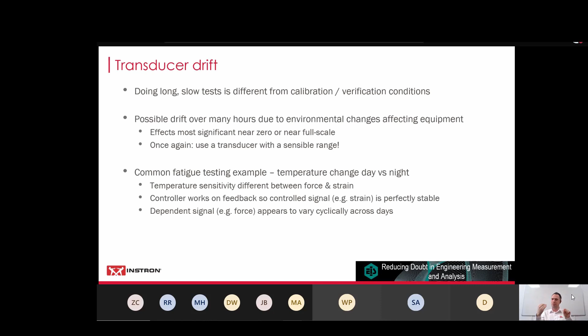Strain gauge devices, as I say, drift very slightly with room temperature. Historically, if you talk to people who've been in this business a long time and have tried to do very precise measurements, they'll all have examples where they do a strain controlled test, and the controlled channel will look perfect because the controller does its job and relies on the feedback. The trouble is that feedback is drifting slightly up and down between day and night. So they'll see the dependent channel, the force peaks for each cycle, for example, drift up slightly during the day and drift down slightly overnight. There are always ways and means to deal with these things, but it's a common thing historically.